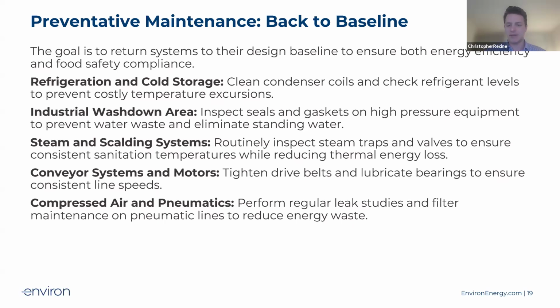So first, as simple as it sounds, your refrigeration is a core part of everything that you do. Having a preventative maintenance schedule that is annual and ideally quarterly, checking on those condensers so that, A, the coils are clean and the set points are established correctly and actually reading the actual temperature, is the clearest way to prevent costly temperature excursions, in terms of wild temperature swings, that obviously we don't want to see.